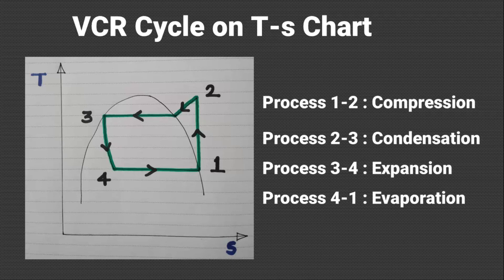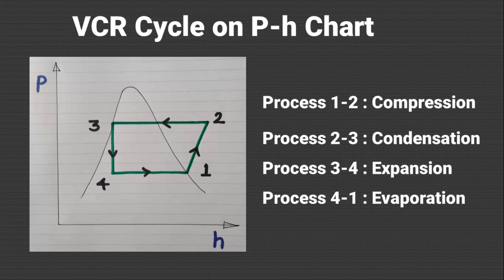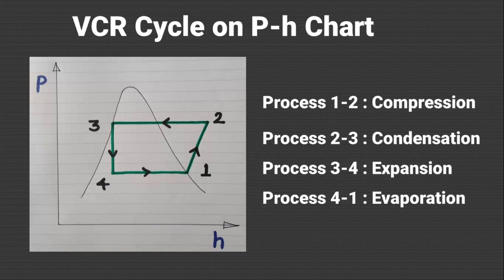The same vapor compression cycle on the P-h chart is shown in the next slide. Here the specific enthalpy is plotted on the horizontal axis and pressure is plotted on the vertical axis. The same 4 processes are shown in the graph. Process 1 to 2 is the compression process where pressure increases and work is done on the refrigerant, so enthalpy also increases. From 2 to 3 is the condensation process where the refrigerant condenses at constant pressure. From 3 to 4 is the throttling process, which is isenthalpic and shown as a vertical line. From 4 to 1 is constant pressure evaporation of refrigerant in the evaporator.